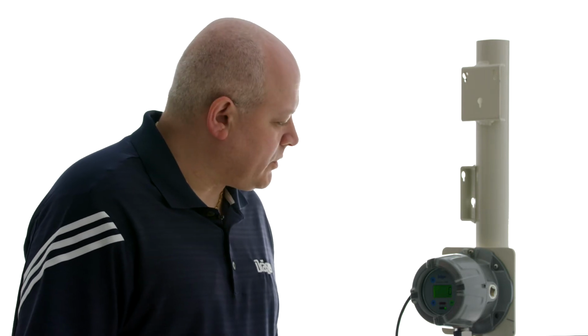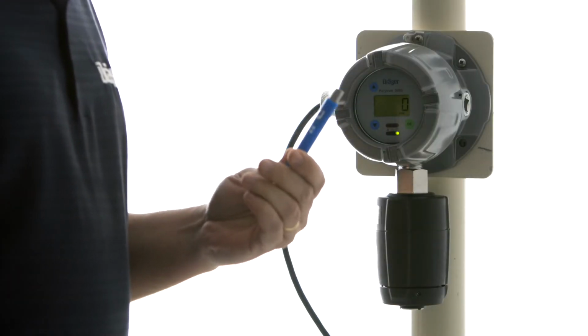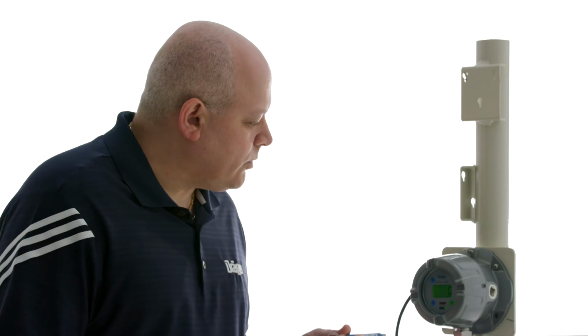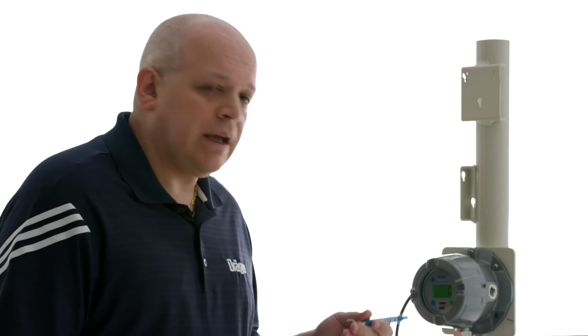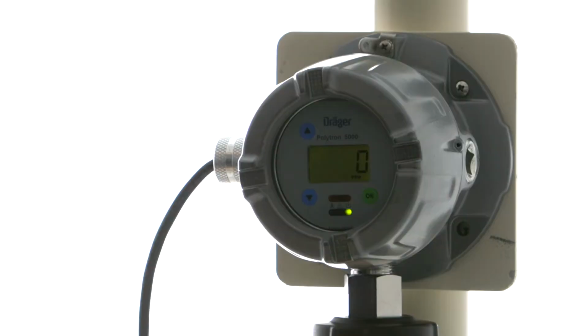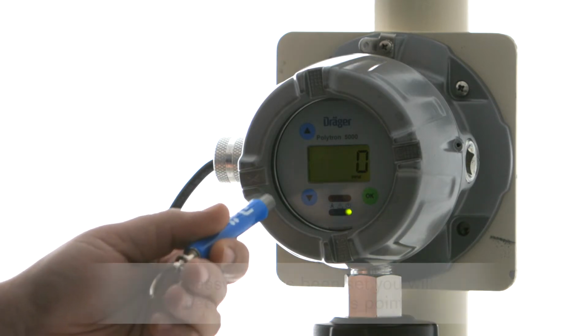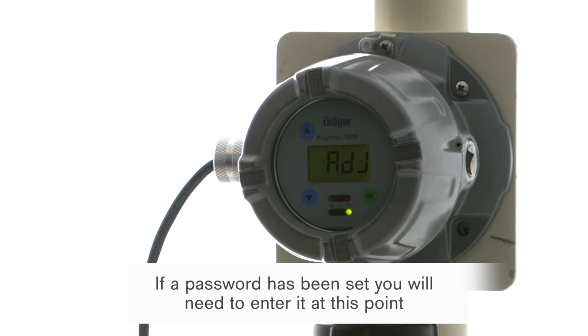We're going to go through and talk about how to get in and out of the menu of the Polytron 2000. You will use a magnetic stylus to touch on the up, down, and the OK buttons. The down arrow is used to enter the menu, and that's what we're going to do right now. Just press the menu, and the first thing that we see is the zero adjust, which is our zero calibration.